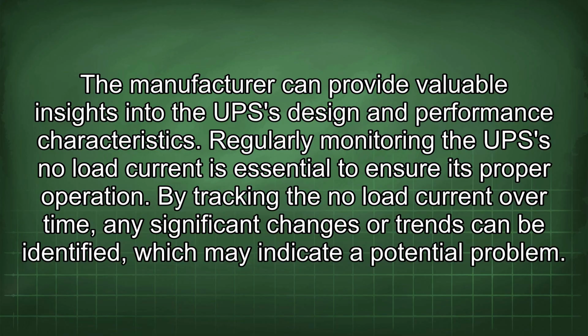Regularly monitoring the UPS no-load current is essential to ensure its proper operation. By tracking the no-load current over time, any significant changes or trends can be identified, which may indicate a potential problem.